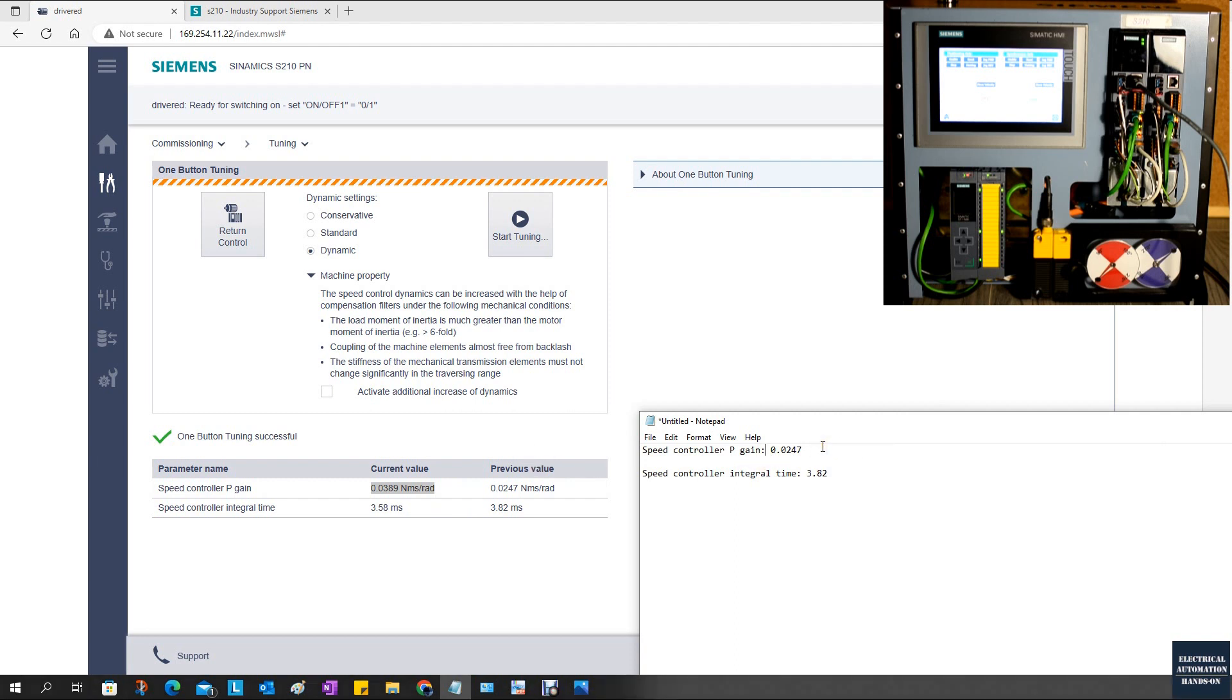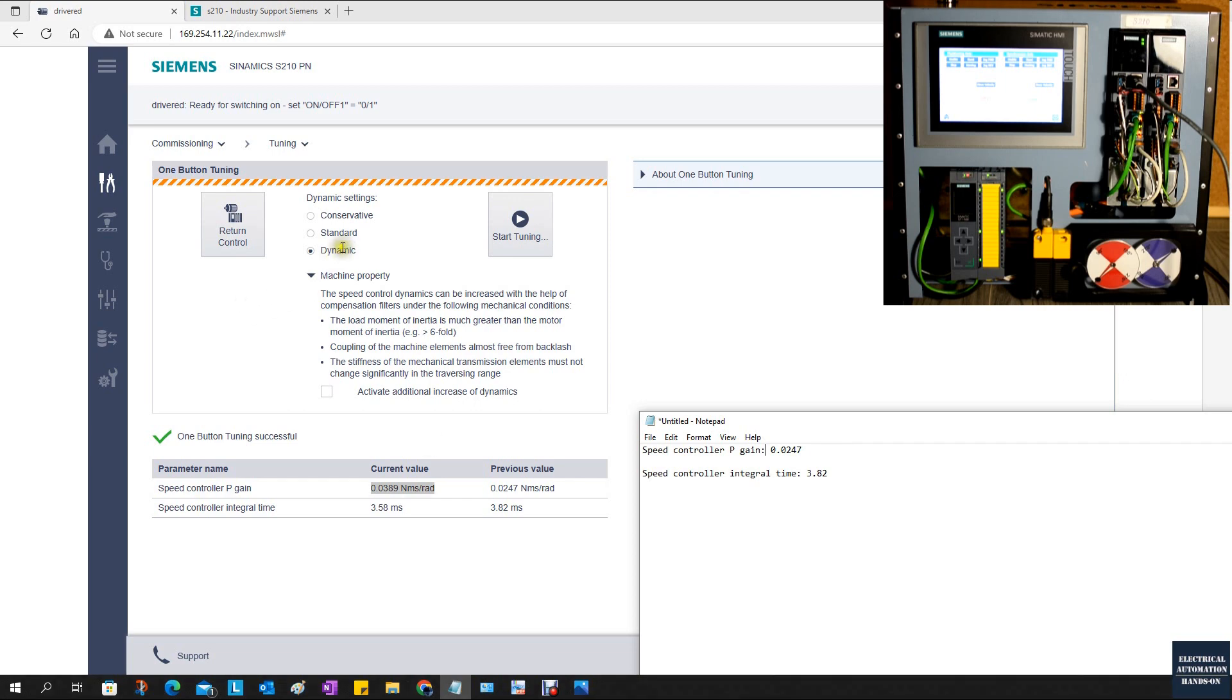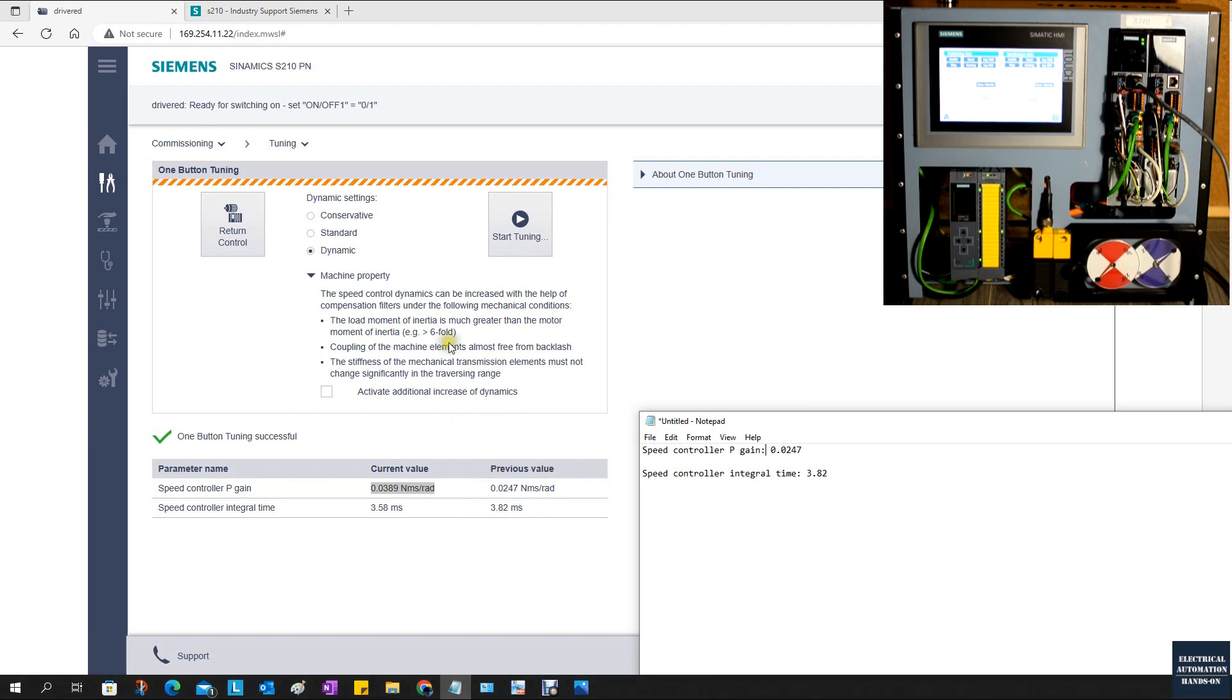Keep in mind, the system is actually also measuring the inertia internally, it's just not showing here. The disk we see here is very light. The load is very light. That's why these two P-gains do not show significant difference. But once in a real case, you are connecting the real load. After you click tuning, selecting dynamic versus conservative, the P-gain will show significant difference.